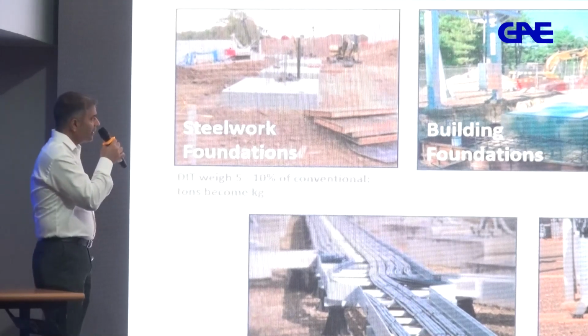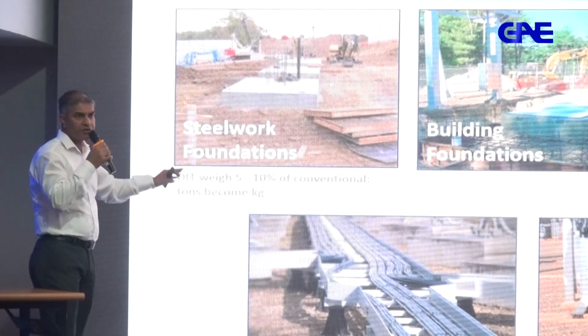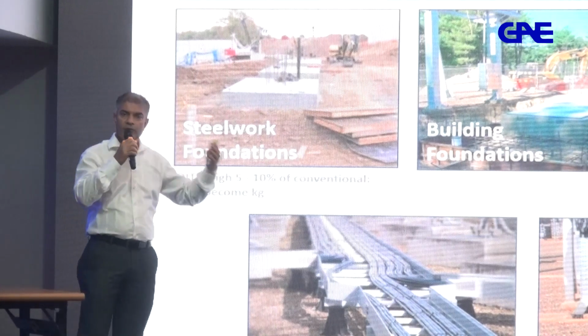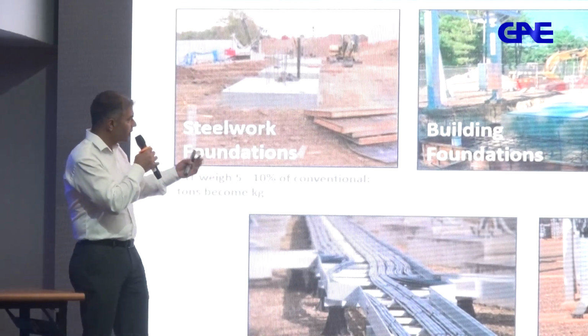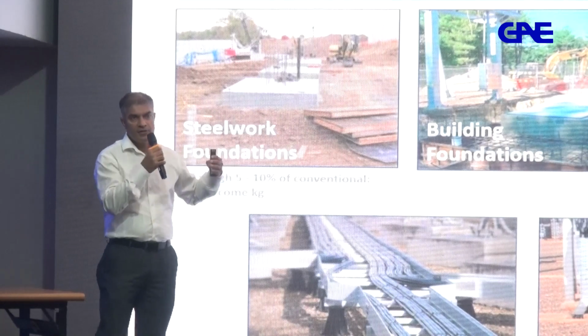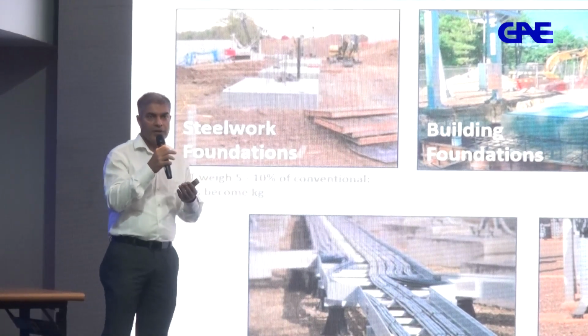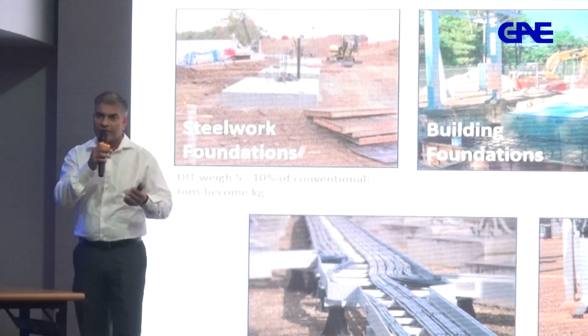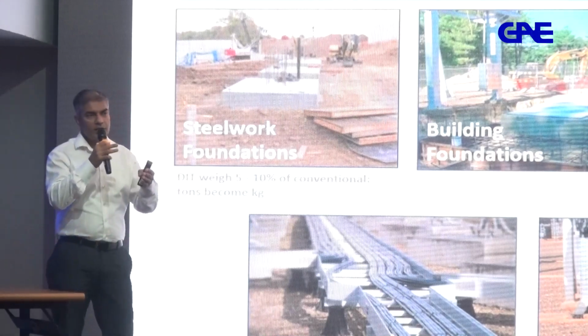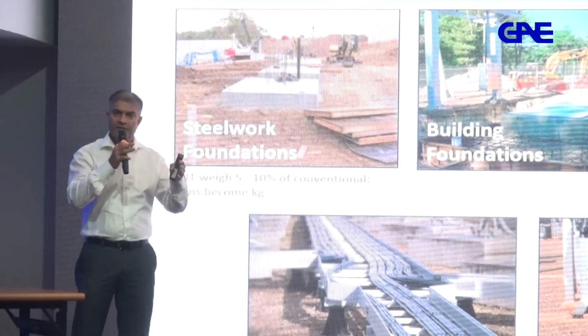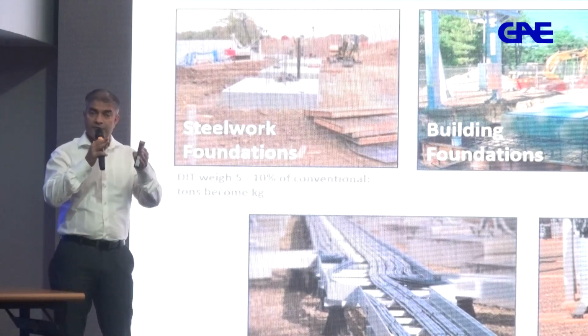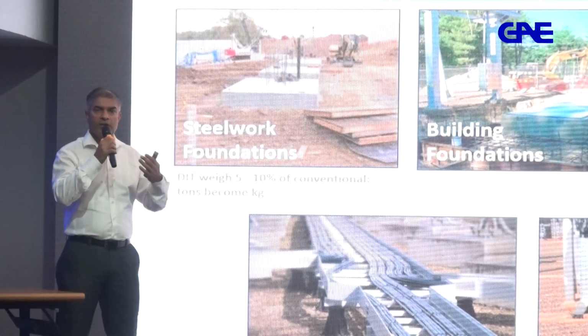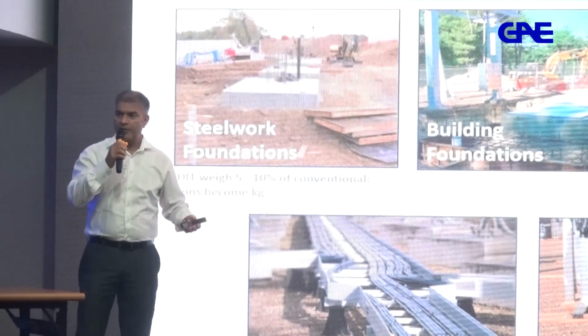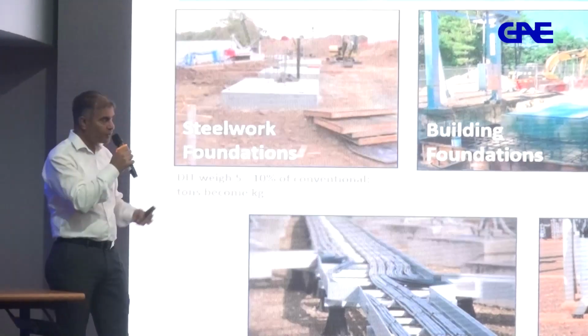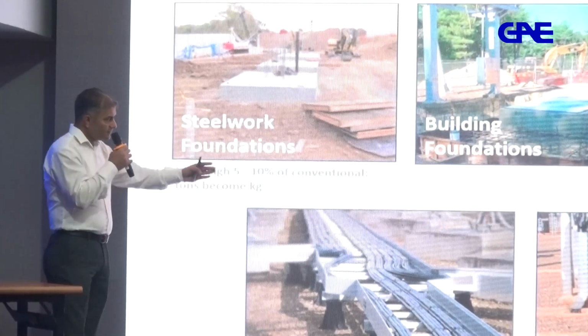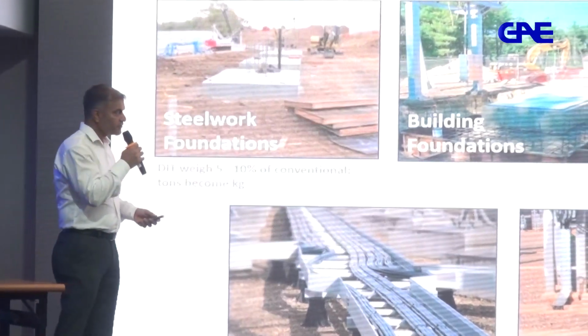Okay, so engineering optimization: steel work foundation, if you use optical CTs, VTs, of course you can reduce that. Building foundations, cubicles, they can be considerably smaller because you have nothing but power supply and fiber optic. So you can accommodate many relays in one panel because the relays are smaller. So why do we need a big number of panels as we have in conventional substation? You don't need cables, ducts, everything can be reduced.